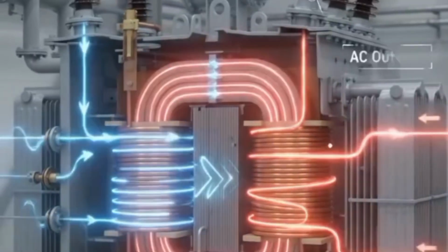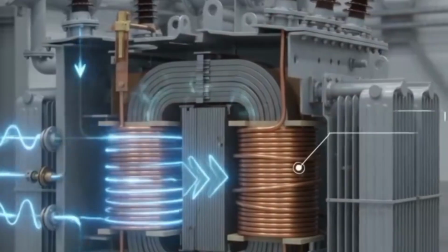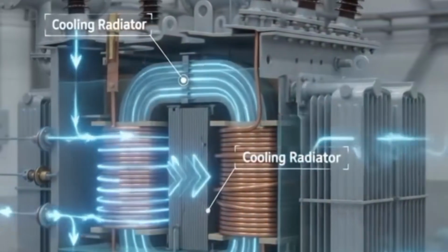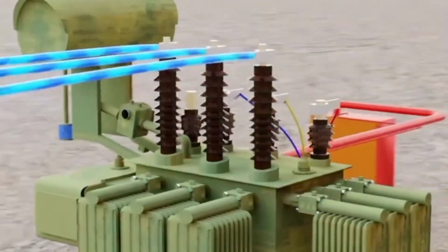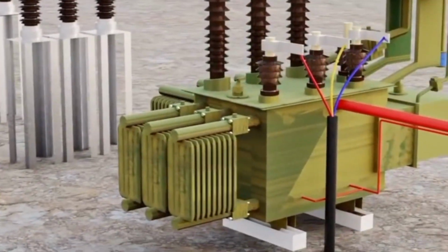It prevents electrical arcing inside the tank and absorbs internal heat, carrying it toward the external radiator fins where it can be cooled by the surrounding air or heavy-duty fans. A small tank mounted on top, called a conservator, provides extra space for this oil to expand and contract safely as temperatures fluctuate throughout the day. Through this harmonious combination of internal electromagnetic physics and robust external engineering, power transformers maintain the invisible lifeblood of our modern cities, working tirelessly behind the scenes to keep our world illuminated.